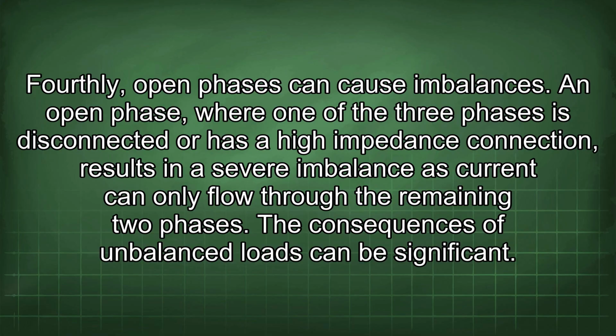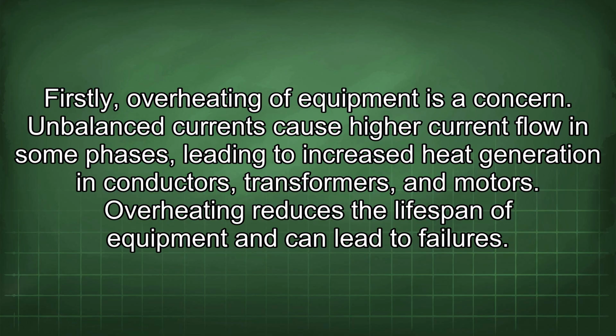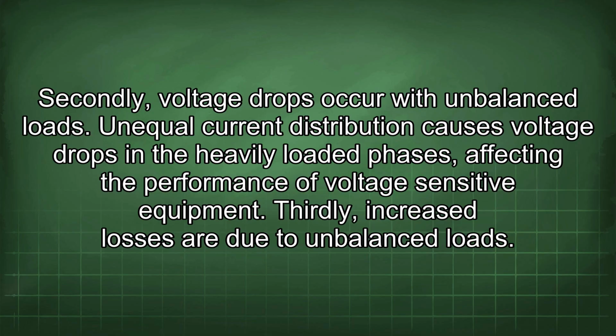The consequences of unbalanced loads can be significant. Firstly, overheating of equipment is a concern. Unbalanced currents cause higher current flow in some phases, leading to increased heat generation in conductors, transformers, and motors. Overheating reduces the lifespan of equipment and can lead to failures. Secondly, voltage drops occur with unbalanced loads. Unequal current distribution causes voltage drops in the heavily loaded phases, affecting the performance of voltage-sensitive equipment.